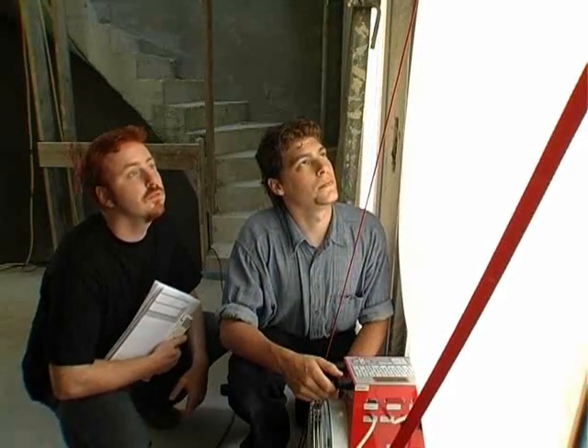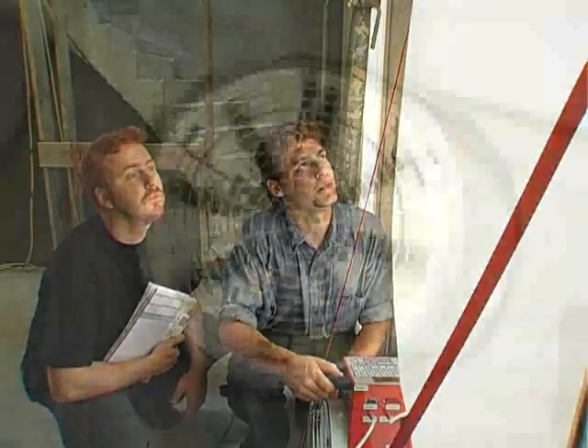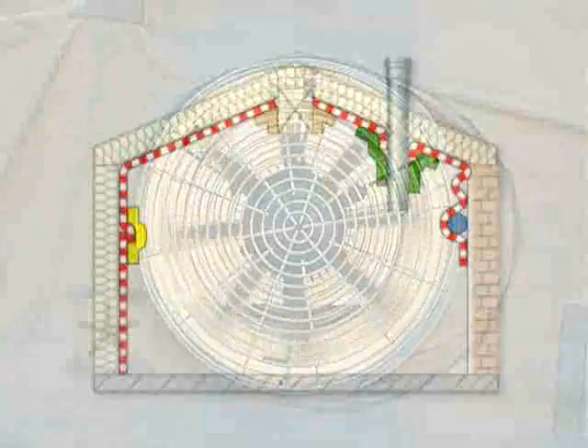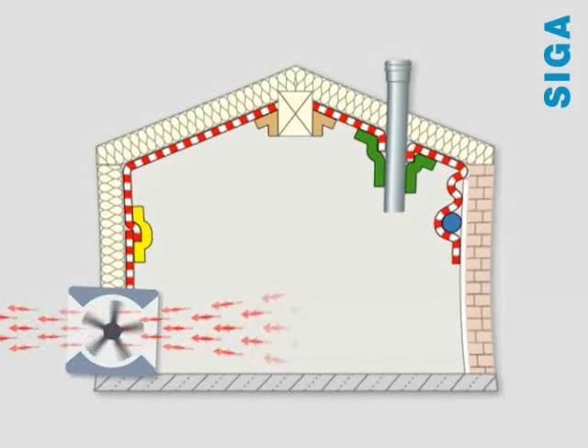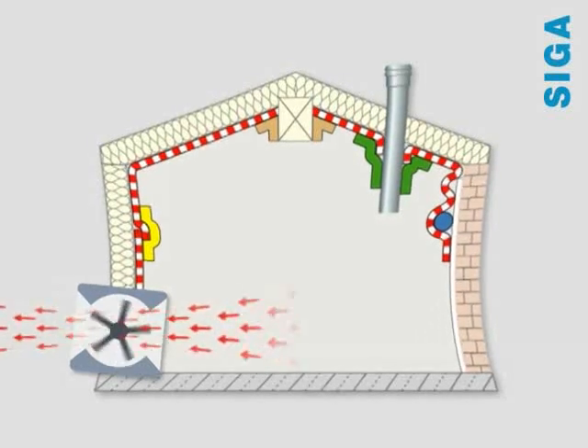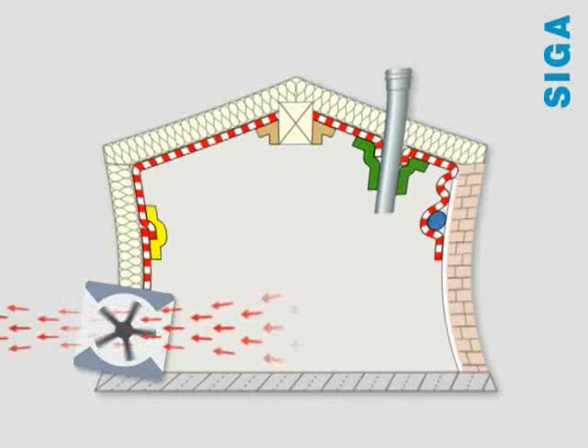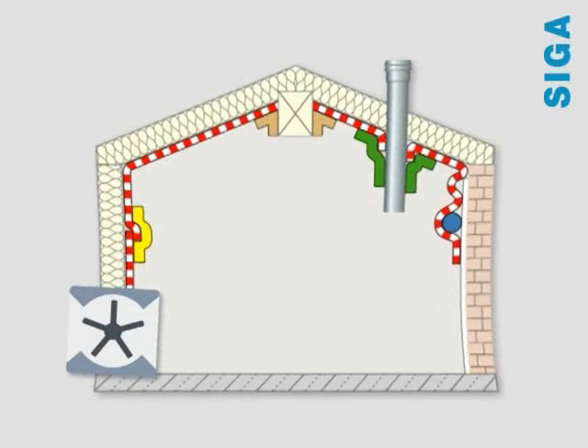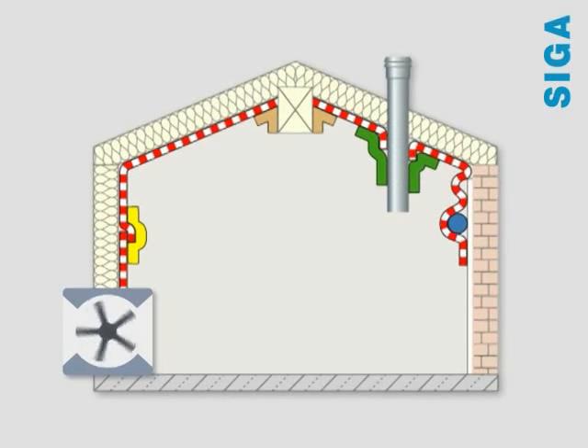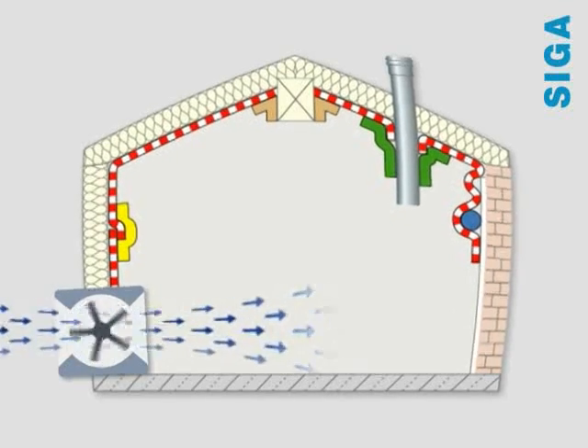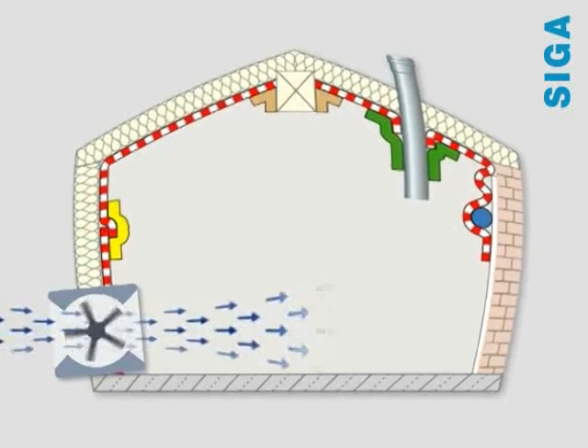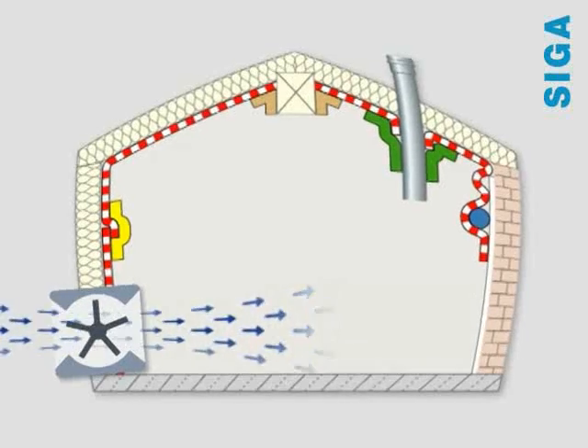Negative pressure builds up inside the structure and the membrane at the measuring apparatus bulges inwards. The fan blows the indoor air out of the structure to produce a negative pressure of 50 pascal in the interior. It then pumps outdoor air into the structure to produce a positive pressure of 50 pascal in the interior, which corresponds approximately to gale force 5.